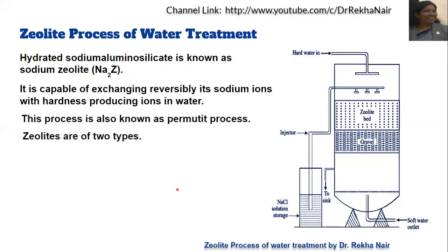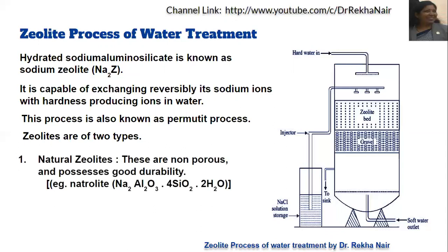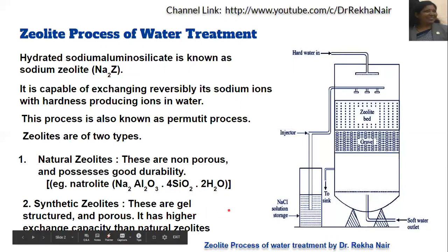This process is also known as the permutit process, and we have two different types of zeolite: natural zeolite and artificial zeolite. Natural zeolite has the formula Na₂Al₂O₃·SiO₂·4SiO₂·2H₂O. These are non-porous and have good durability. The synthetic zeolites are gel-structured and porous, and have better exchange capacity as compared with natural zeolite.